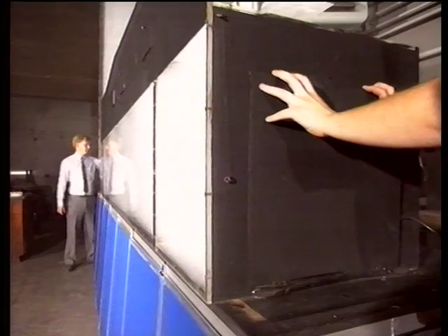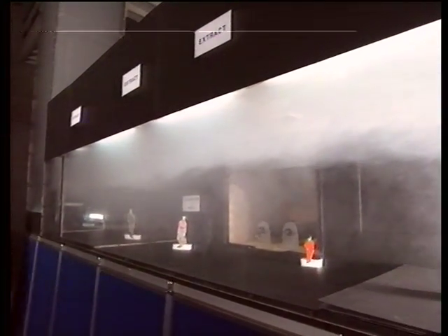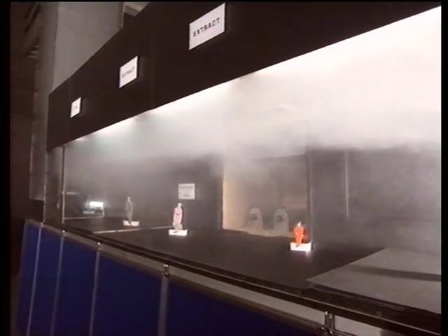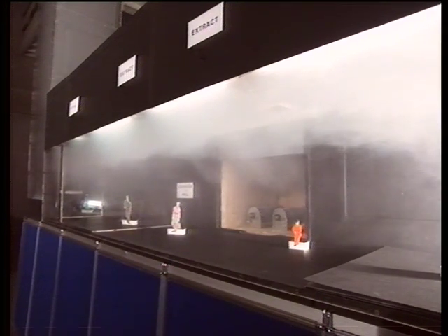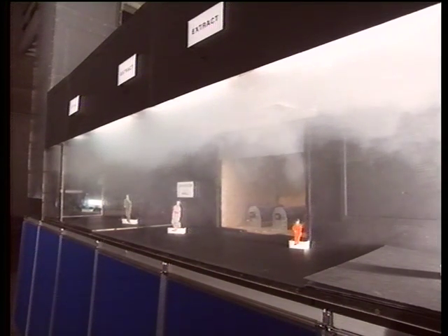Well, the common method for large undivided volume buildings is to use a ventilation system and reduce its spread. Firstly, you need to divide the ceiling up into smoke reservoirs. That means you need screens. Secondly, you need adequate air to come in at low level, and that means you need openings at both ends. Thirdly, you need adequate extraction in order to ensure that the gas lays well above the escape route. By doing these three measures, i.e. opening the inlets, having screens and having adequate extraction, you can see that this gas layer has gone well above the escape routes within the mall.